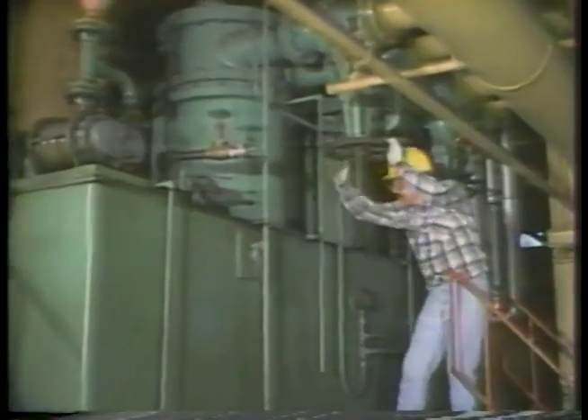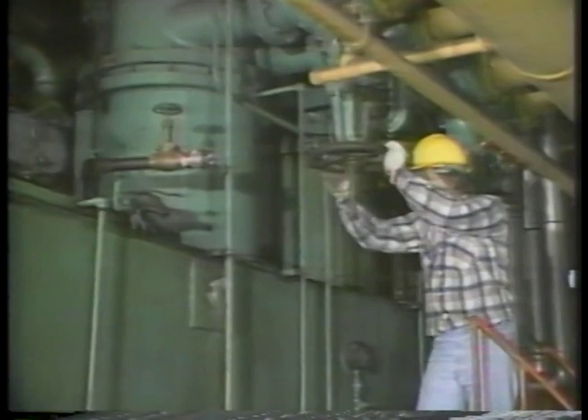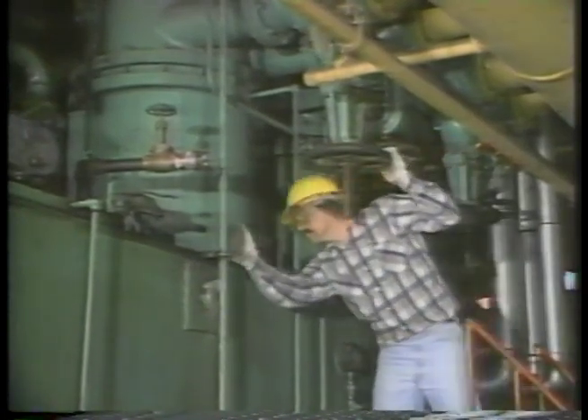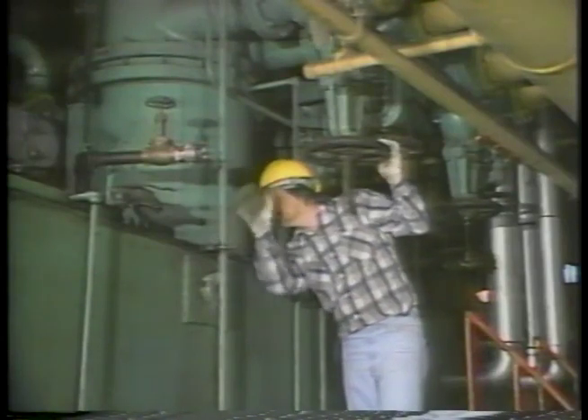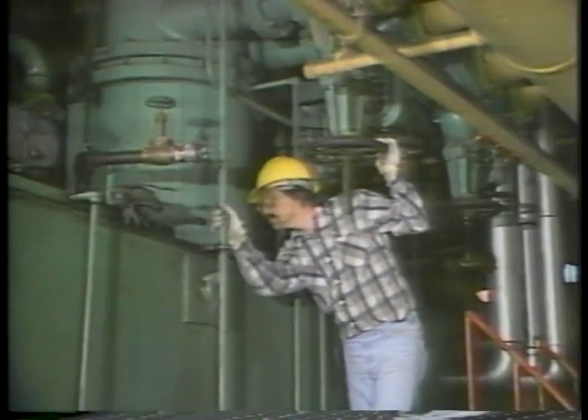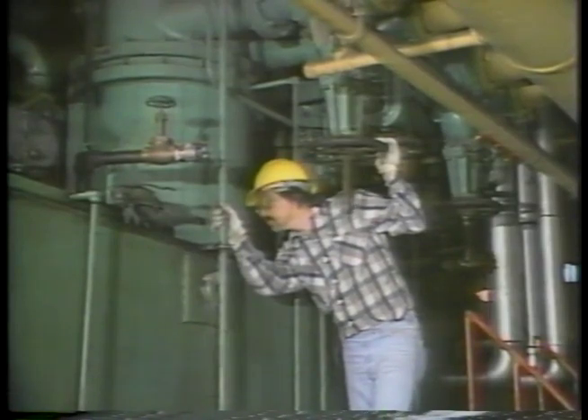A valve on the cooling water outlet is opened or closed in response to the oil temperature. If oil temperature increases beyond the desired value, the cooling water outlet valve is opened a little more. This increases cooling water flow. The increased flow causes more heat to be removed from the oil, and bearing oil temperature decreases.